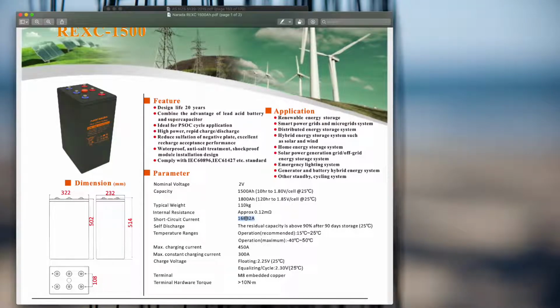That's the bolted fault current, and the definition of a bolted fault current is on the battery side of any protection that's installed by the installer. If you were to replace it with a 0 ohm resistor, basically a spanner, what would the current be? So yeah, a short circuit right across the battery system. Now, when you've got a series string of batteries, the fault current doesn't go up. The voltage goes up, and the arc flash incident energy goes up, but the fault current is the same. It's the same current passing through all the series cells. But when you have two strings, you're doubling the bolted fault current.